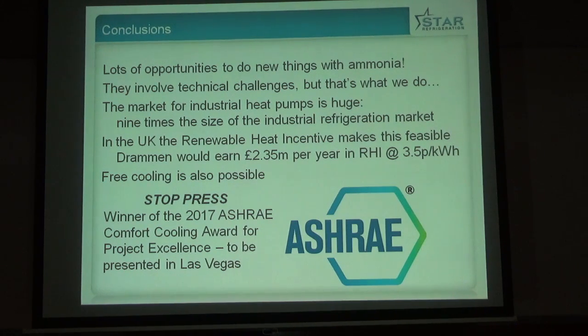and just wouldn't deliver. So if you take the whole picture, as I said, when NASA looked at the International Space Station, they picked ammonia as the refrigerant because it was the best choice. People have been using it as a refrigerant since 1857 because it's really good. And it's not because they've got some kind of strange addiction to it, or a quirky mentality that says, I'm going to do Everest the hard way. It's because it's really good. So that's why it's widely used in industrial refrigeration. It's not used in domestic because the circumstances are not suitable. The level of maintenance required wouldn't be available in the domestic situation, so it's rightly kept out of that.